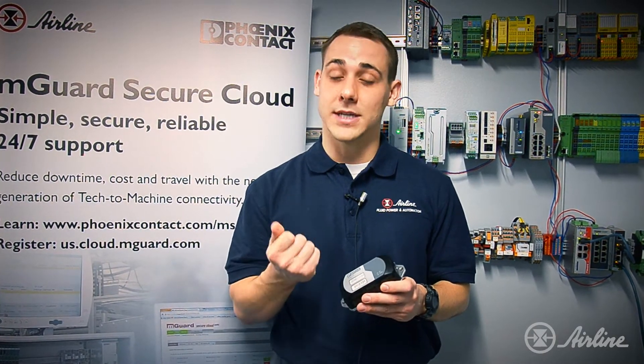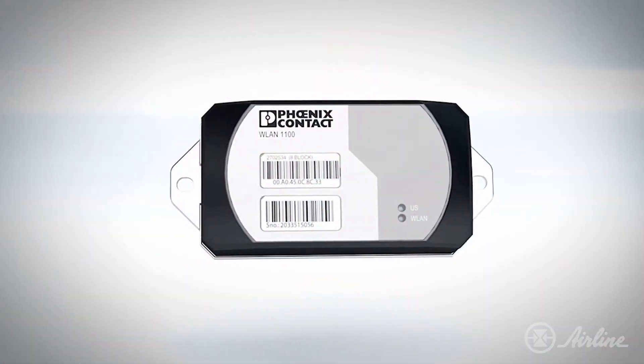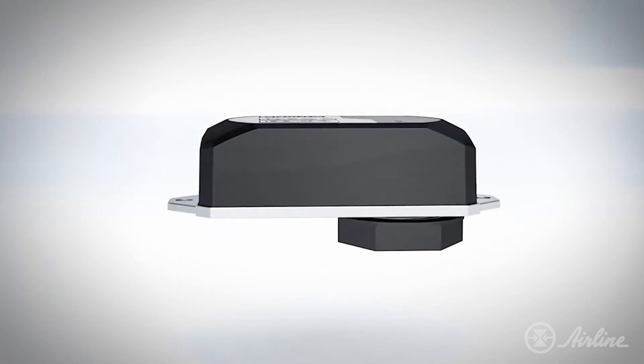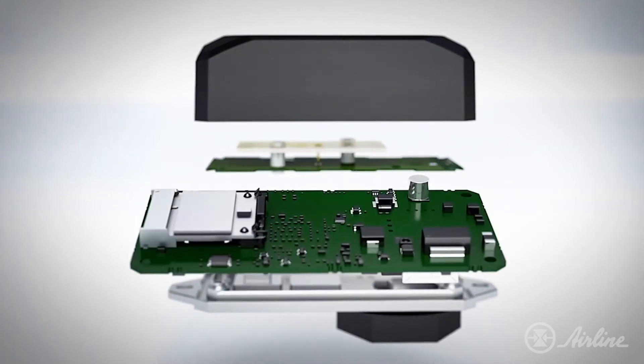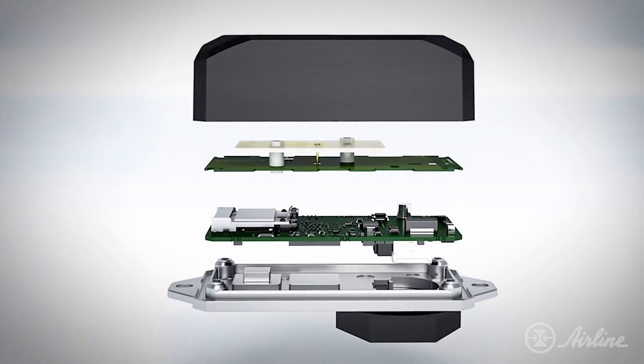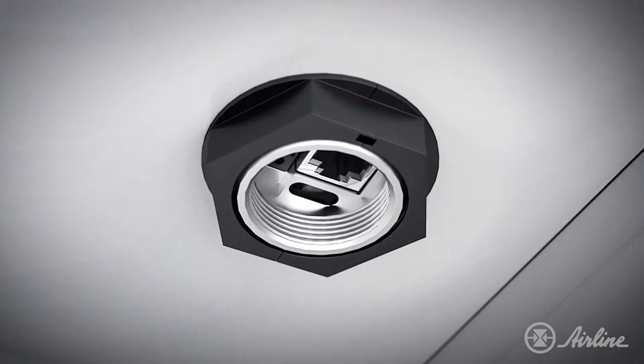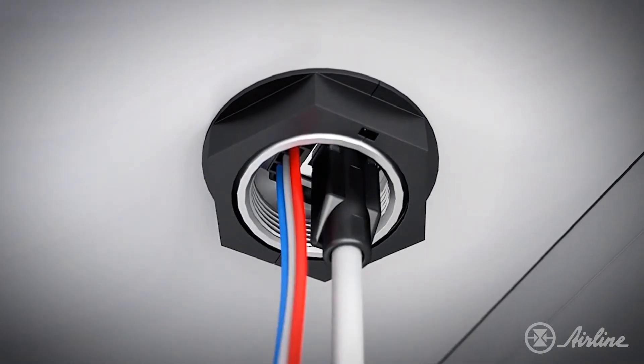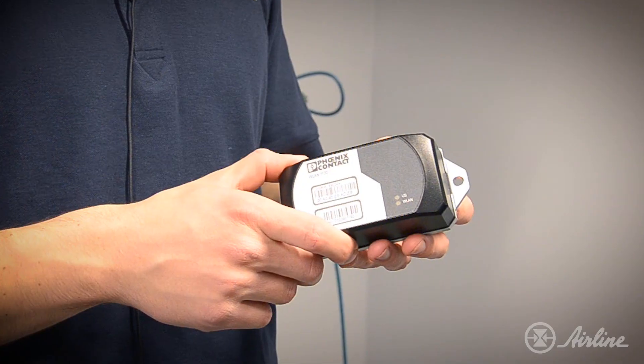Conventional WLAN system designs typically require a DIN-mounted wireless radio as well as antenna accessories mounted on the outside of the cabinet. With the 1101, you have both the wireless radio and antenna integrated into one IP-rated housing. Inside the rugged housing, the WLAN 1101 utilizes existing 802.11N wireless technology and combines that with two 5 dBi antennas.